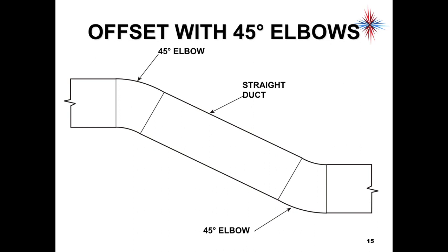So again, let's talk a little bit about what we covered here. We talked about what is a dynamic loss. It's basically anything in a duct that will cause turbulence. It could be a corner, it could be too sharp of an elbow, it could be a small radius turn, where the air is bouncing off the outside and we have pressure differences on the inside. Long sweeping curves for changing direction, no sharp angles, is the best thing we can do for airflow.